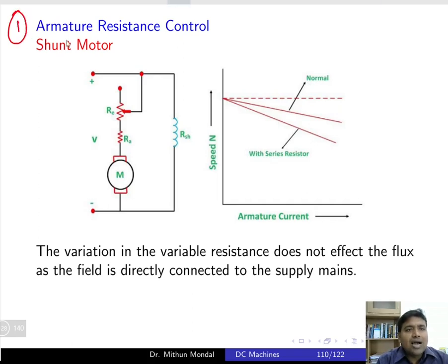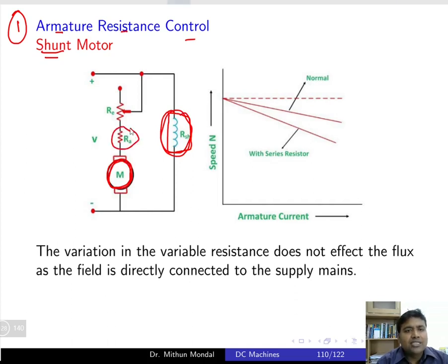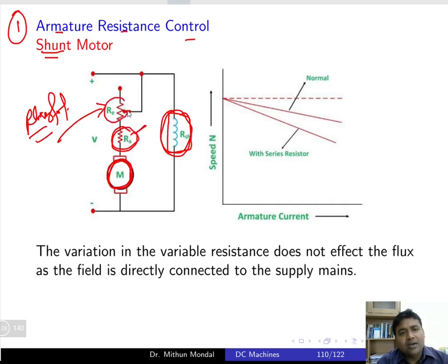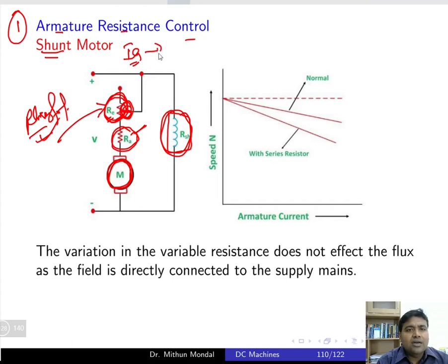For armature resistance control, we consider the shunt motor, where the field winding is connected in parallel with the armature. A rheostat is connected in series with the armature. By sliding the moving contact of the rheostat, the resistance increases or decreases, controlling the armature current.